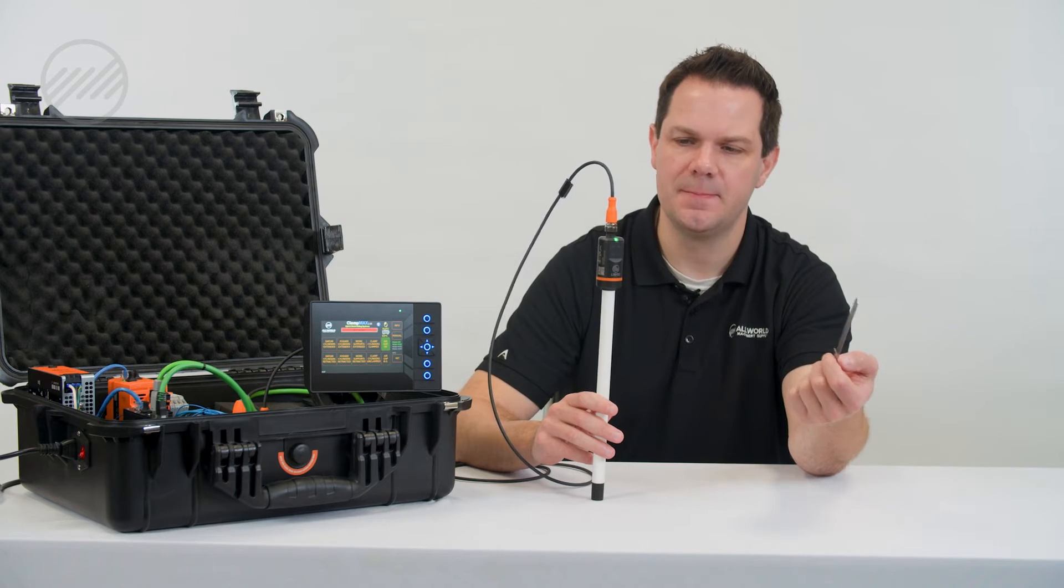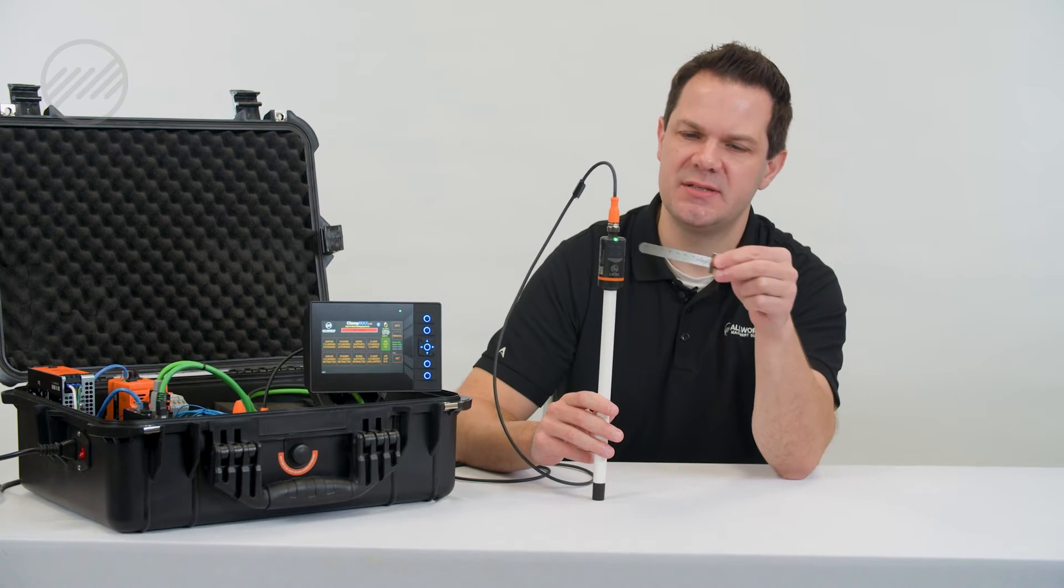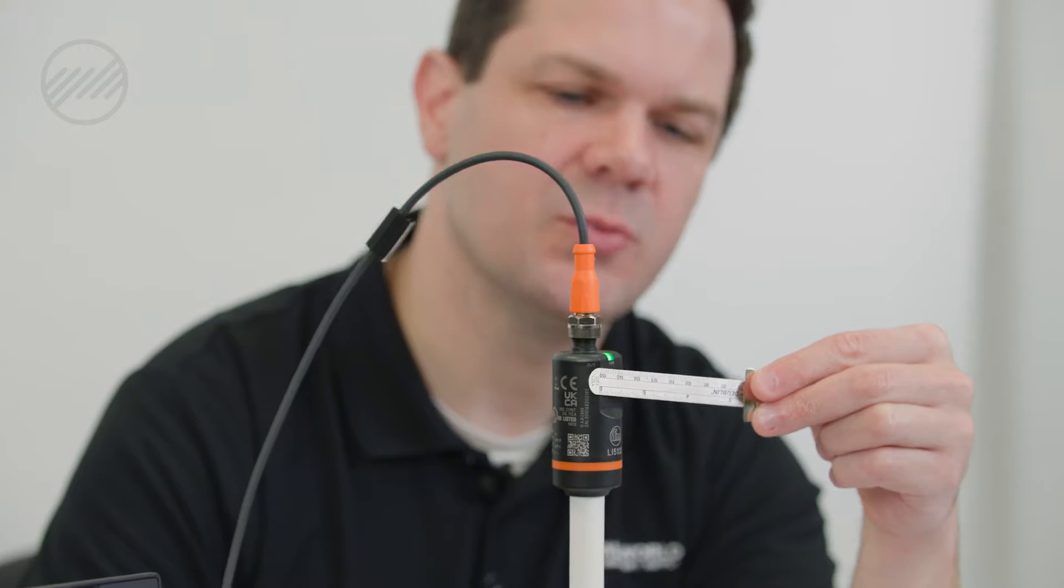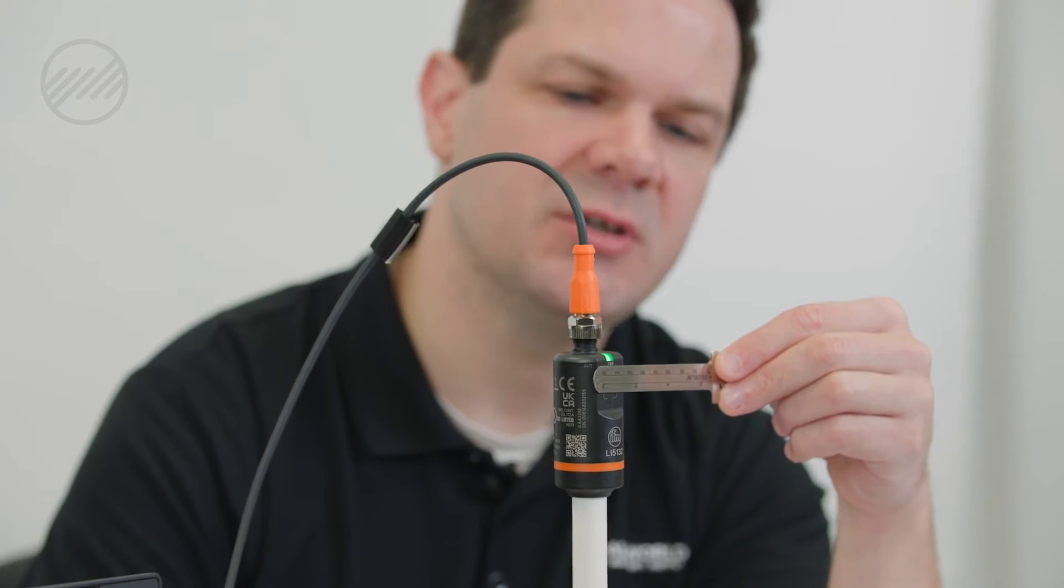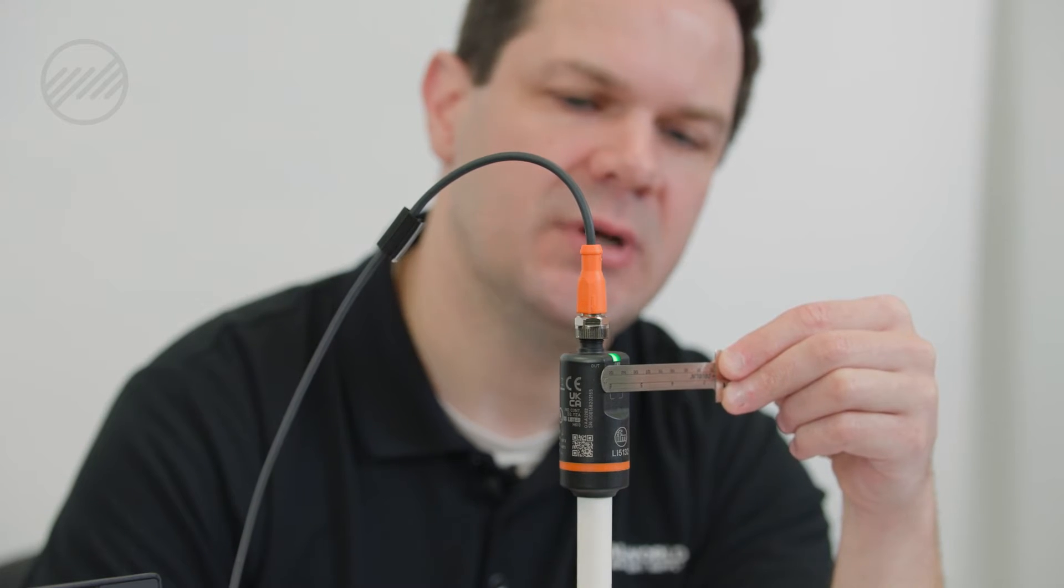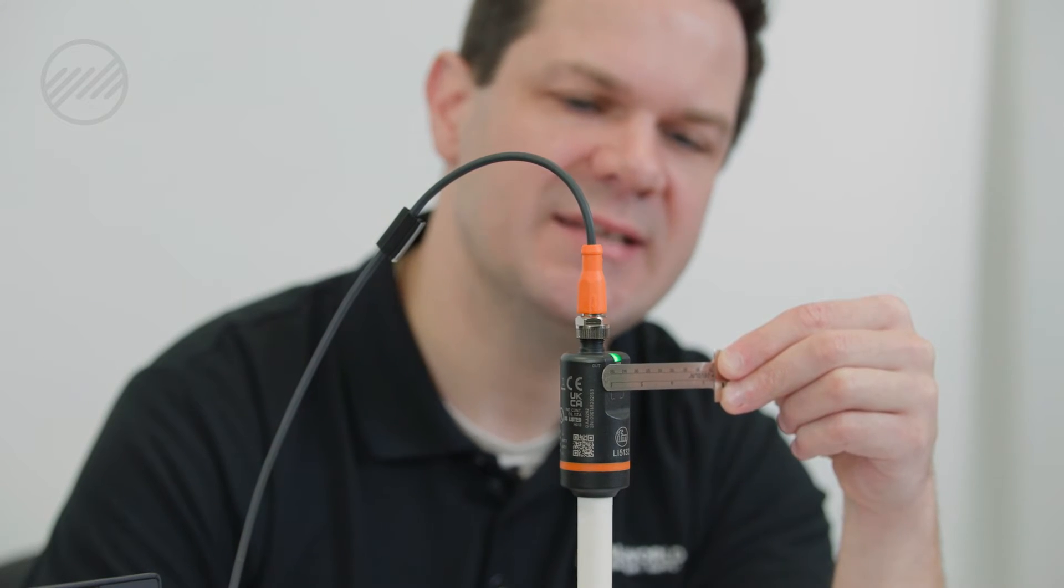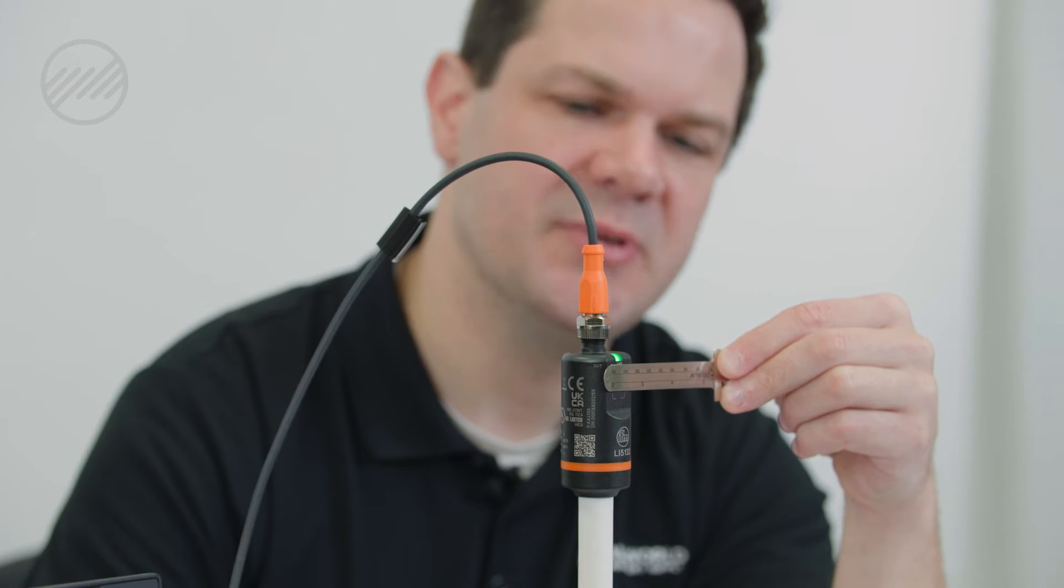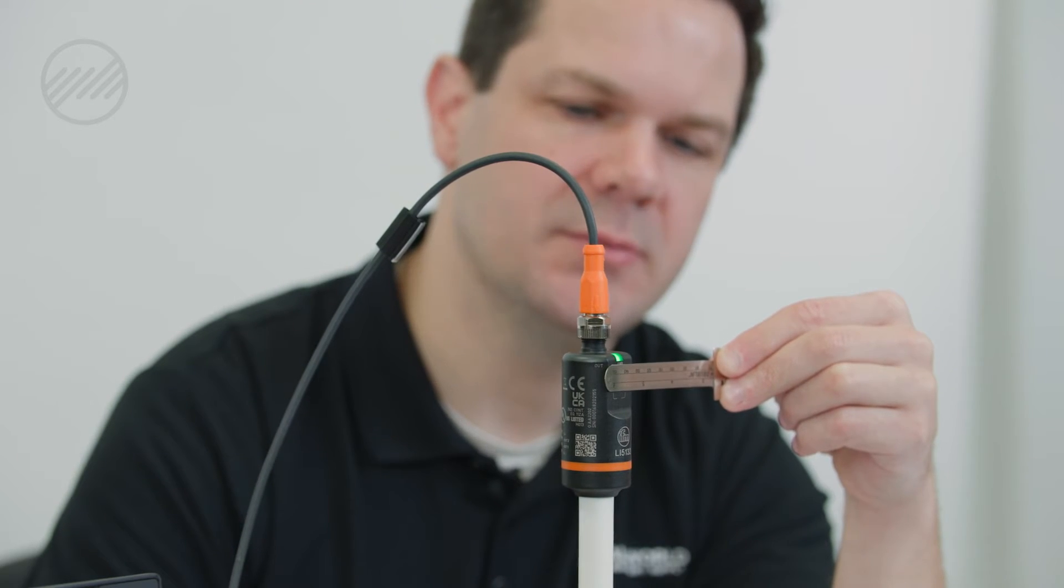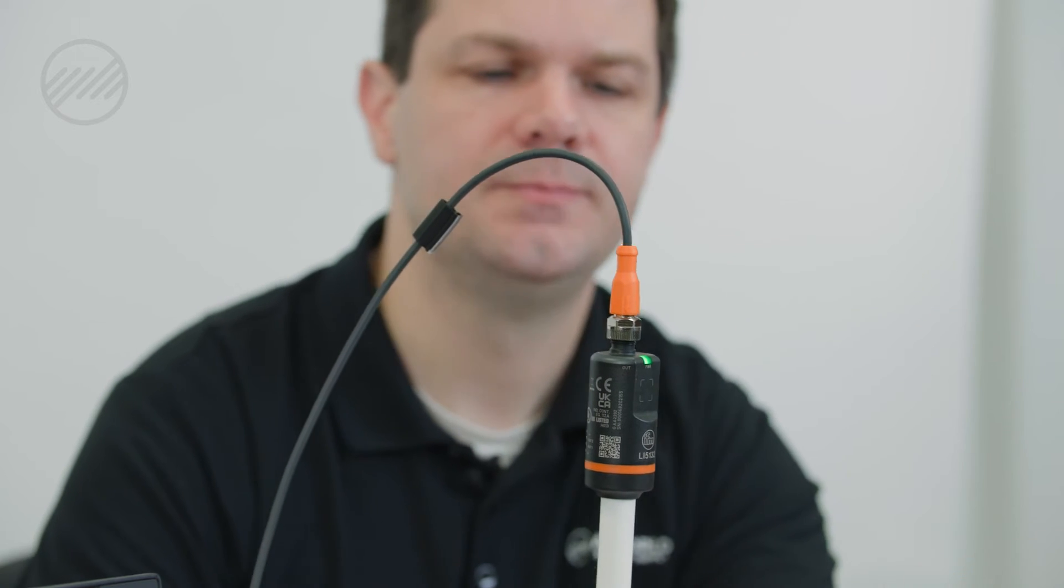I'm using a scale, but we need to take a metal object and hold it over the face of this switch and it'll start to flash on your indicator. It should flash about 10 times. The last one will be a double flash, which will indicate that we're in teach mode. We're there now.